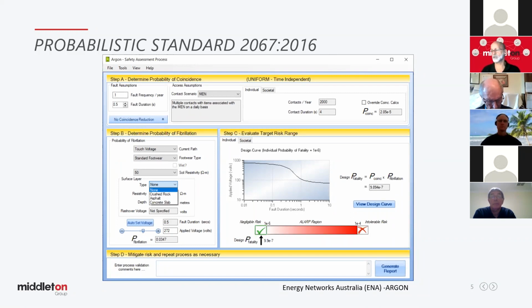So what we aim for here, and what society says, is: look, if the risk is 1 in 10 to the minus 6, or 1 in a million, that's acceptable. Above that, we're in an ALARP, or as low as reasonably practicable, region, up to an intolerable risk. But in design we're always aiming for less than 1 in 10 to the minus 6. That's the software, and once again, it helps us to calculate the allowable voltage, which you'll see down the bottom left there, through a probabilistic method as opposed to the deterministic one seen on the last slide.